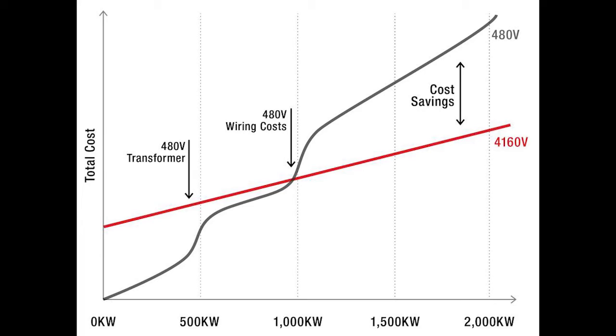So where's the tipping point? Right around 500 kW up to 1 megawatt—that seems to be the crossover point. It depends on your installation situation, how you're running, how much line you have, the distance, etc. But once you get over 1 megawatt and beyond, it's pretty much a no-brainer. At that point the cost savings far outweigh the upfront capital equipment, to the point where you're literally making it back before you even run the heater.